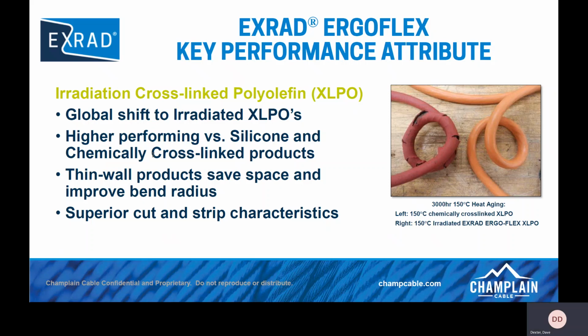Stripping is another performance attribute to consider. Irradiated XLPOs tend to cut and strip cleanly, allowing for proper connector fit, typically with no cut strands. Silicone and EPDM rubber often leave pigtails unless the cutting blades are set very deep, which can lead to cut strands. Additionally, inner tape wraps around the conductor are often used, which can also be problematic in the stripping and connectorization process.